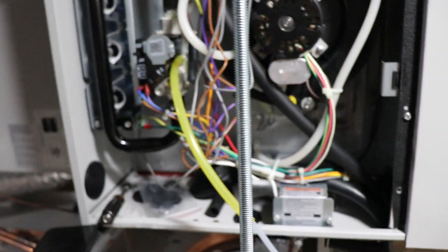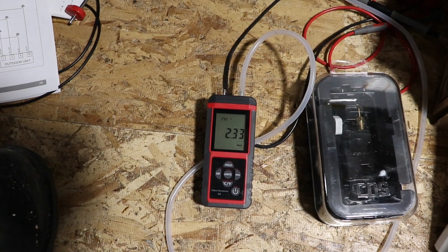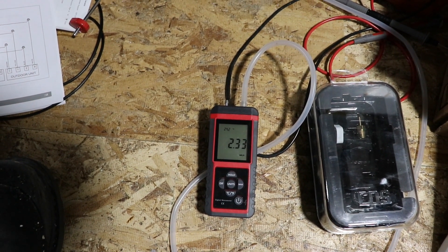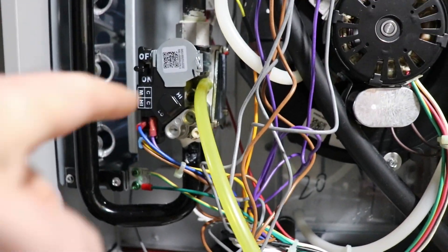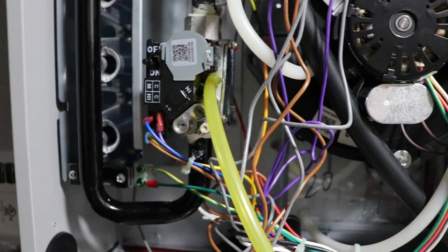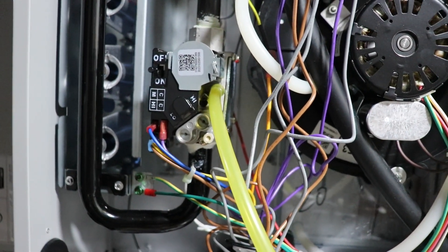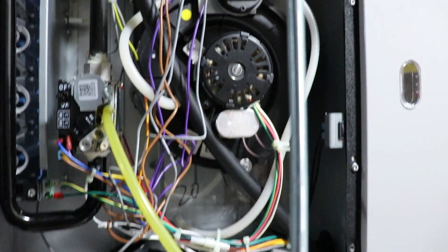To check that pressure for firing, it's at 2.33 inches of water for low. There's a little screw in here. You open it one turn and then you have to hook up to the manometer.